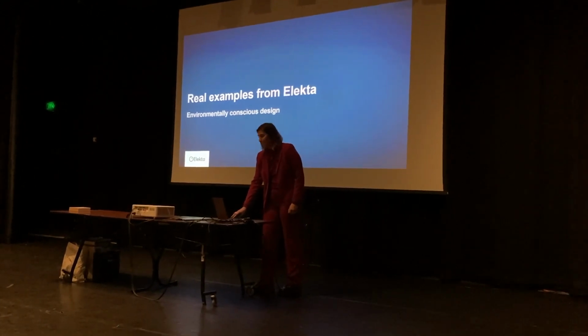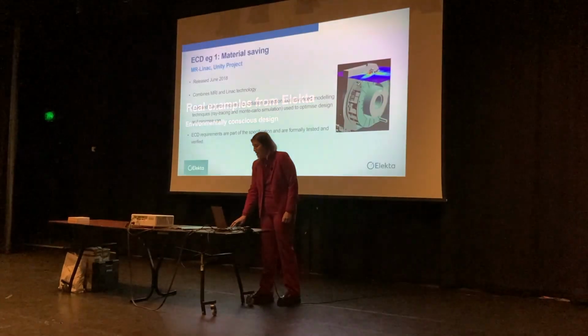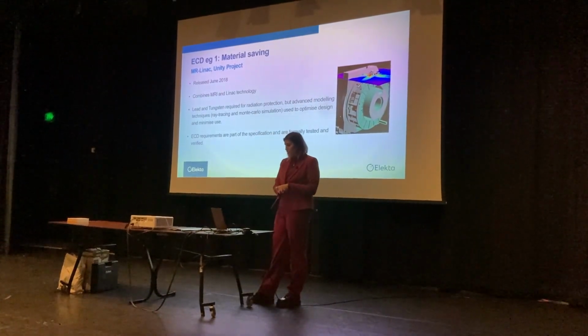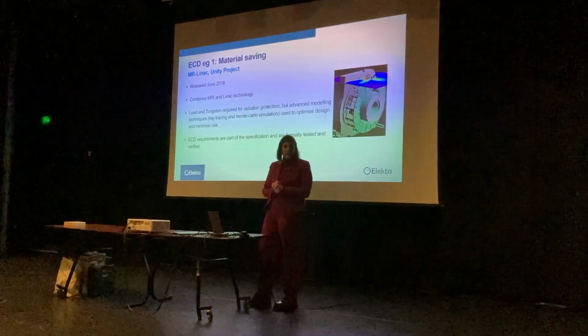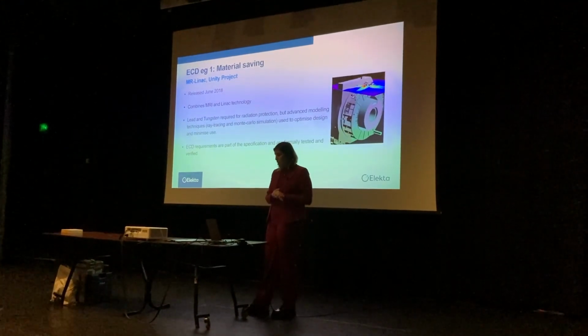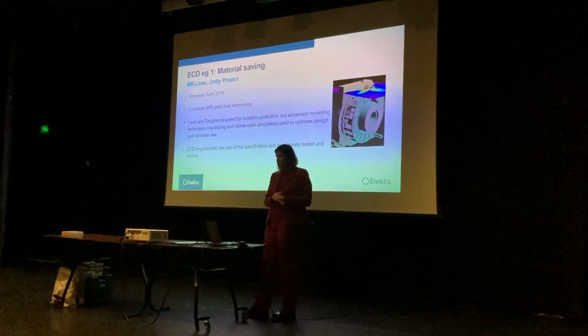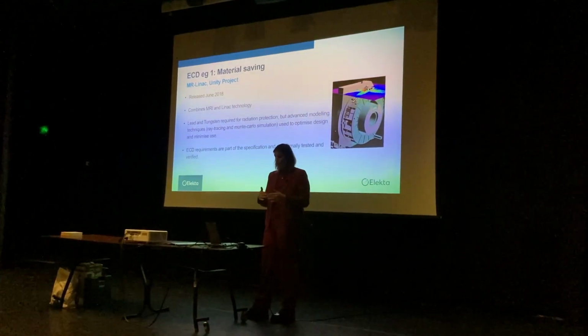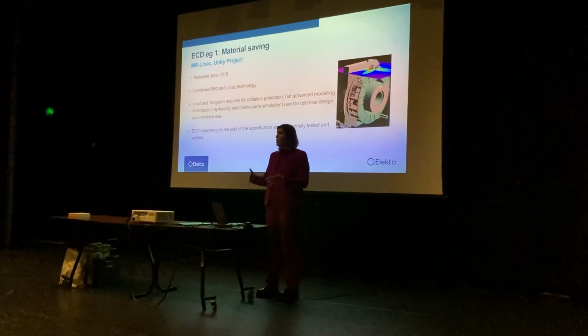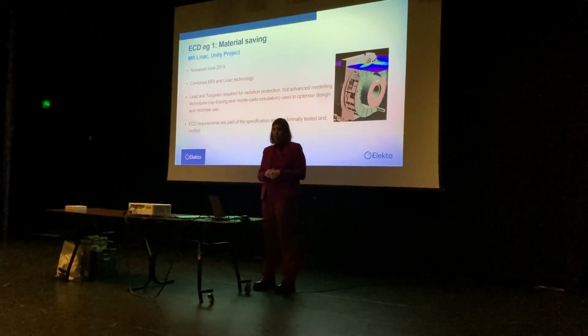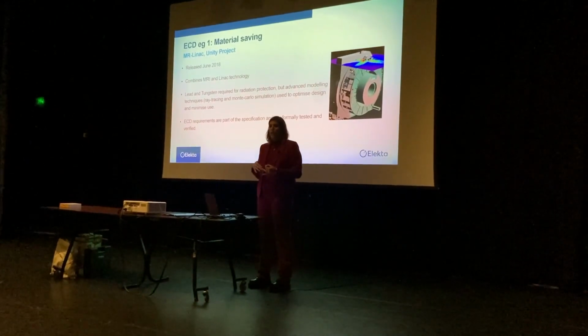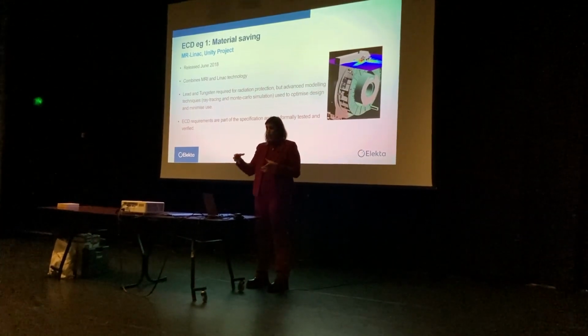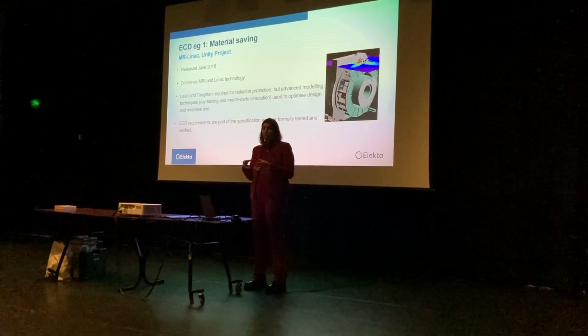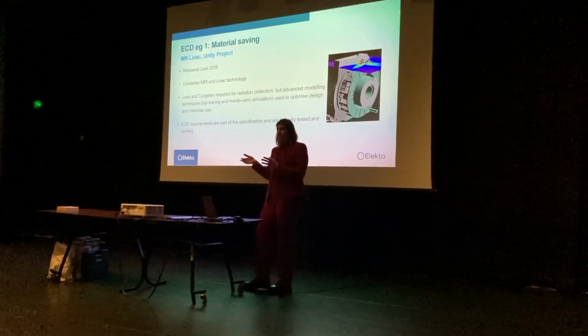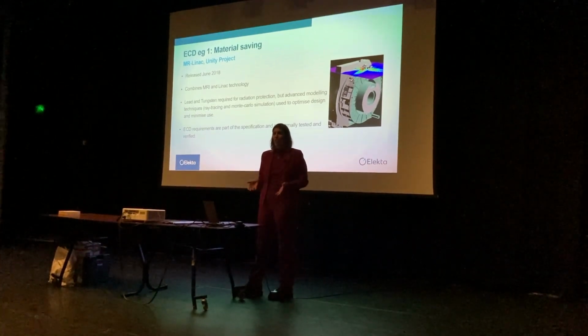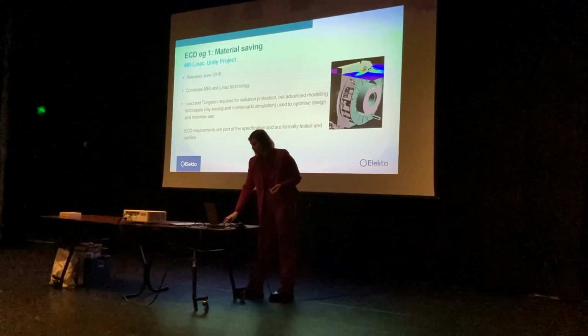I want to talk about some real examples of things we've done that maybe will serve as inspiration. An example of a material saving was done as part of our MR-Linac, our Unity machine that was released in 2018. This was done from scratch as a new development, so there was a target to optimize and reduce the amount of shielding, specifically the tungsten and lead that we use. The team spent a lot of time doing modeling and simulations with Monte Carlo to optimize where you had to place the shielding, to diminish the amounts you're actually using. You've seen the effects of that in the plots and the overall CO2 distribution. So it's a very successful example of something done with intent.